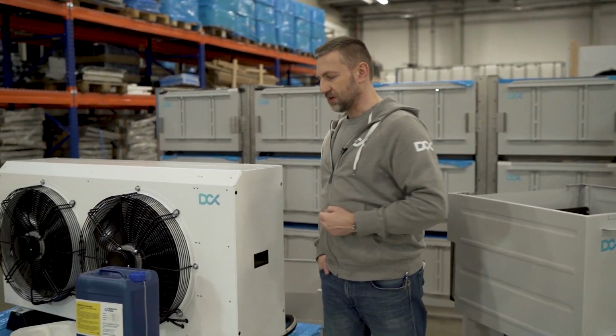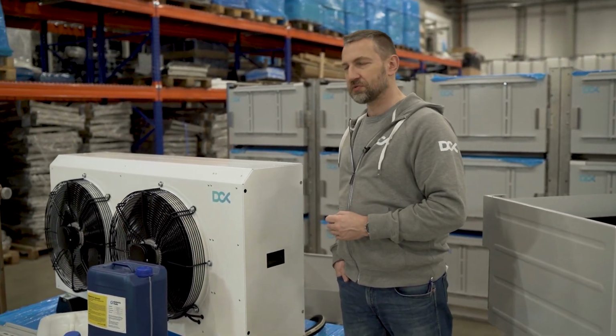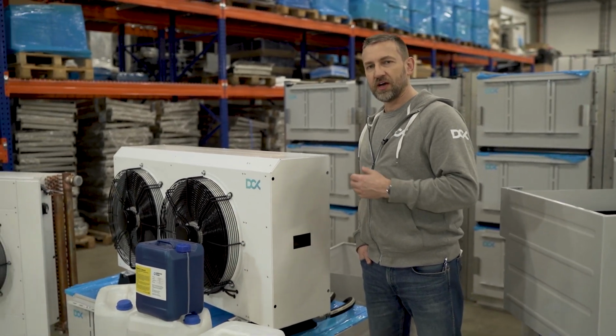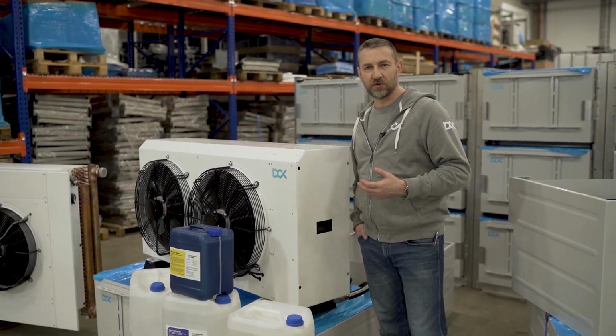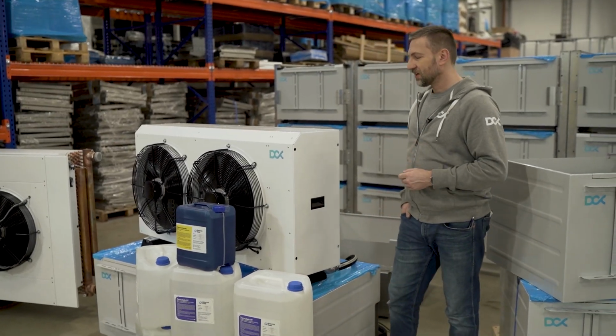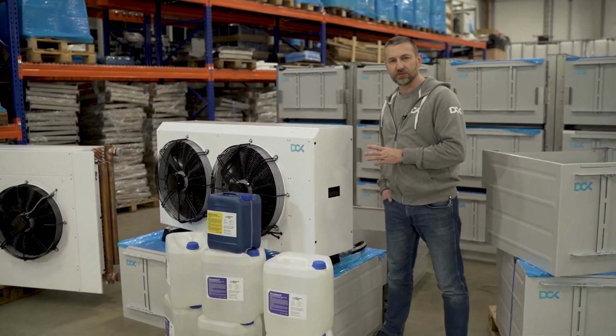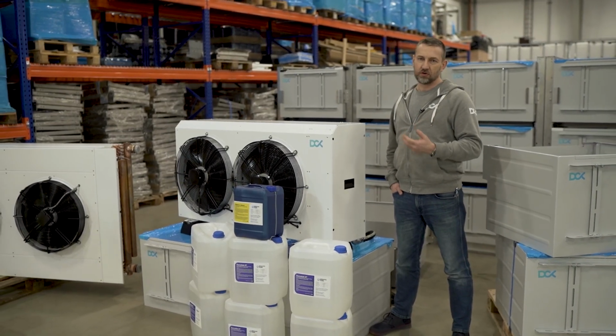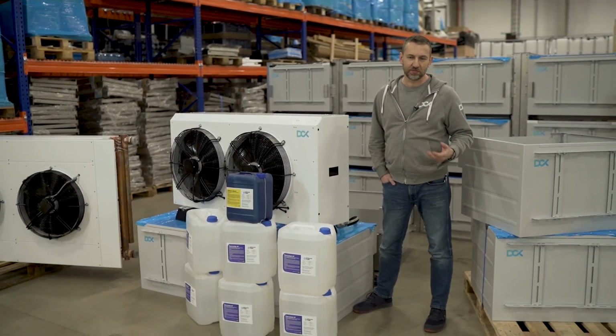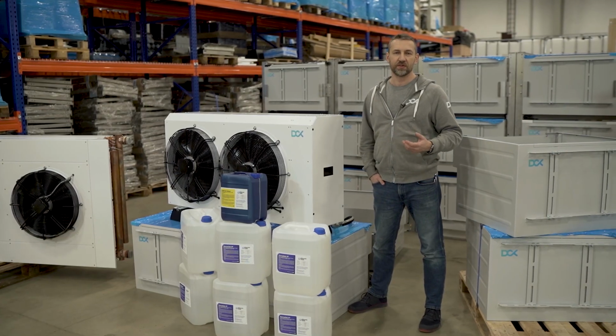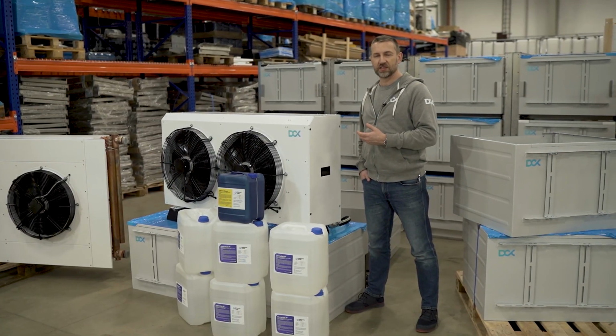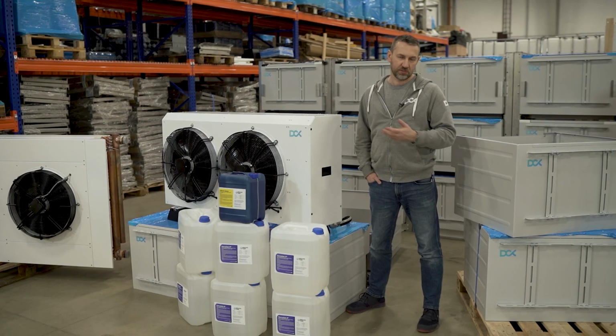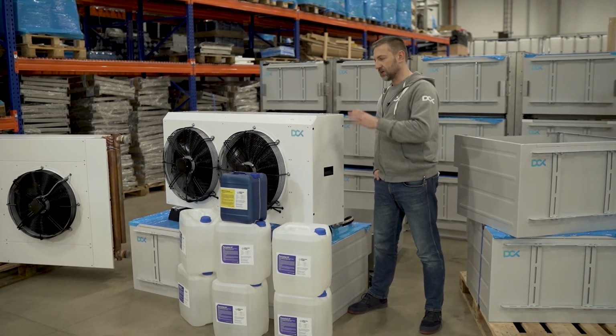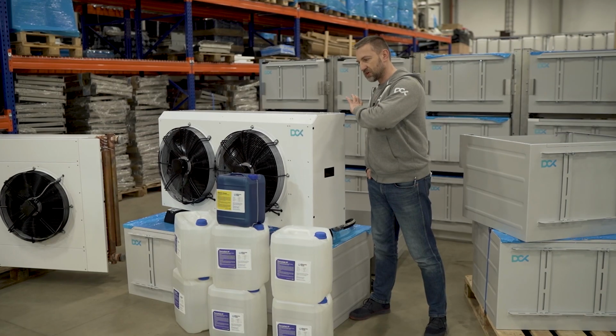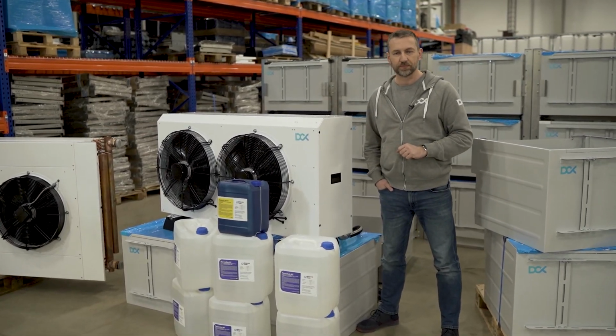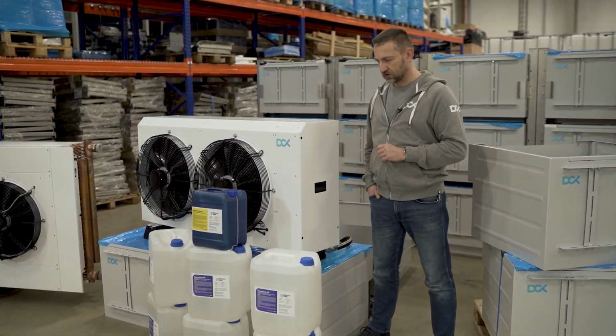It serves one single enclosure fully loaded with the miners being overclocked. So 8 S19s overclocked to 5 kilowatt each one. So pretty hard. And that allows you to transfer 40 kilowatt of the heat from that installation during both the cold season, but also hot summer days. So kind of 35 degrees ambient Celsius, which means 95 Fahrenheit. So during those hot summer days, it will allow you to transfer the 40 kilowatt of the heat from your system, even if you will be using overclock configuration.